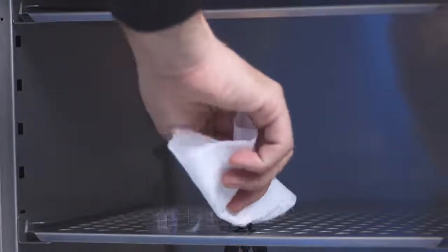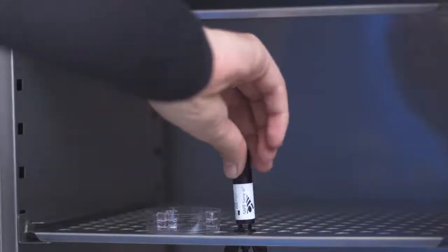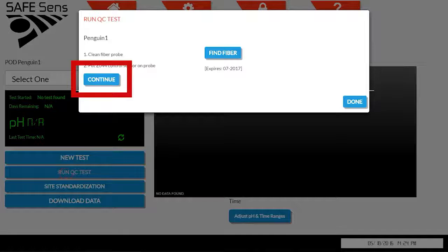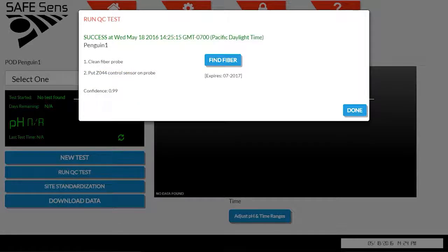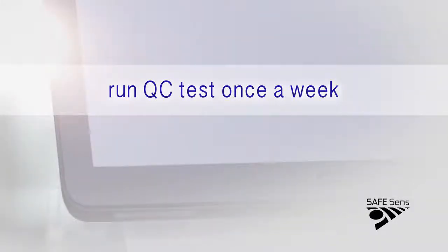The fiber probe can be cleaned with a dry tissue, like a Kim wipe, to remove anything that blocks the optical path. Then put and hold the matching QC control sensor onto the probe and press Continue. The TrakPod quickly checks that the fluorescent signal still matches the initial factory settings and reports a confidence number close to 1. It may be off a little, but if the instrument indicates pass, then the signal is okay. If any differences in the signal exist, the TrakPod will automatically make the necessary internal adjustment. The QC test should be run once a week when you change pH sensors.